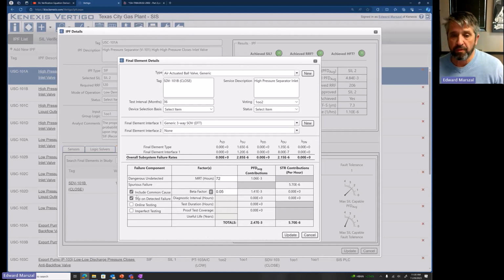We don't do that type of advanced degradation, because although we could do it, the PFD change associated with that advanced degradation is going to be many significant digits irrelevant. So if your PFD is 1.01 E minus 2, if you did that kind of analysis, it would be 1.01000002. So it's not really relevant. So basically, we're doing a true.